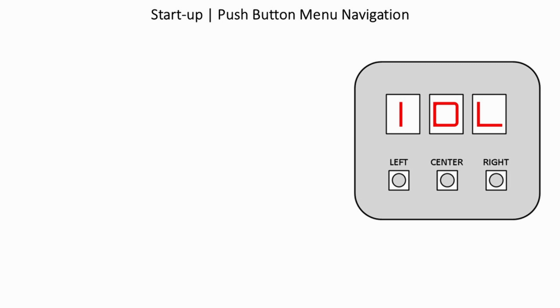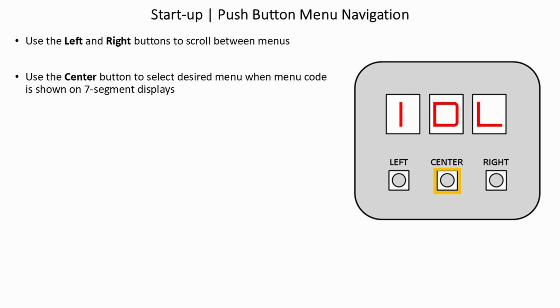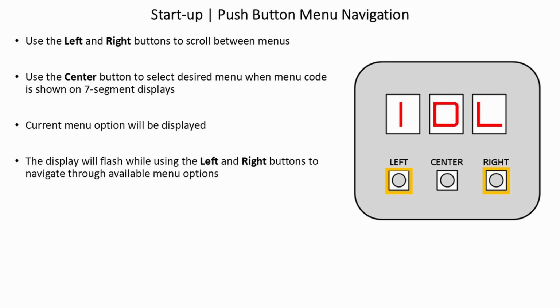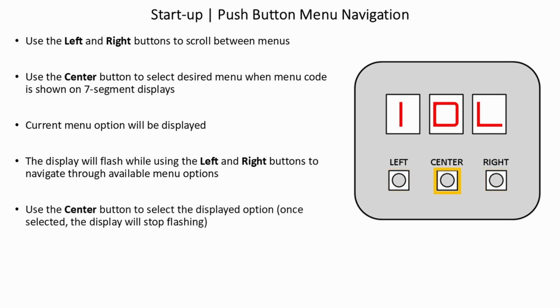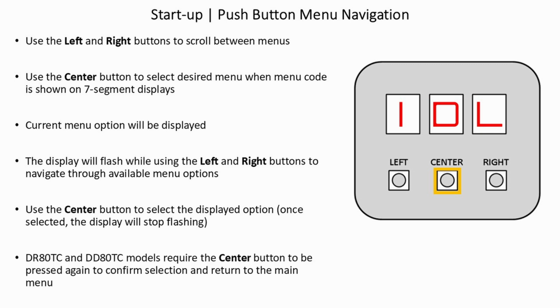Startup, push-button menu navigation. Use the left and right buttons to scroll between the menus. Use the center button to select the desired menu when the menu code is shown on the 7-segment display. Current menu options will be displayed. The display will flash while using the left and right buttons to navigate through the available menu options. Use the center button to select the displayed option. Once selected, the display will stop flashing. DR80TC and DD80TC models require the center button be pressed again to confirm the selection and return to the main menu.